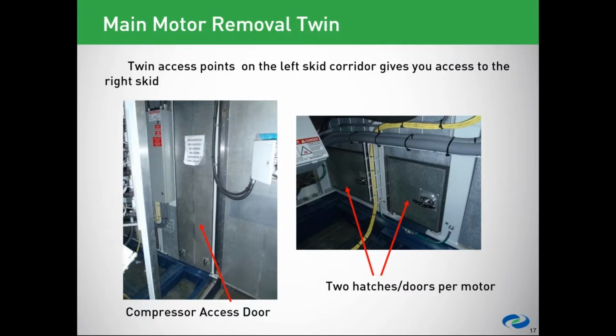So, the main motor removal for the twin. When we do a twin, basically they're pre-positioned on your concrete slabs and spaced about 4 inches apart, and then we can connect those together. Now, to get access to the motor, there are two hatches that we need to open. In order to have that same kind of access when you have a twin, the motor side is what butts up against the other compressor skid. So basically we need to go in through a couple of doors that get added to a twin setup.